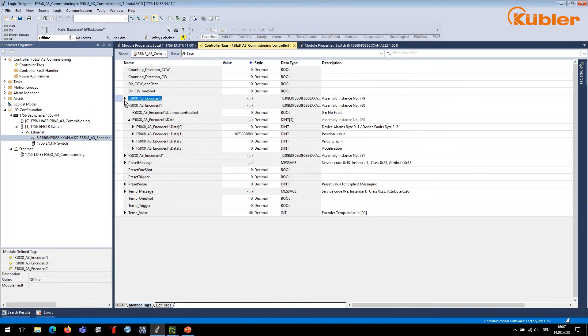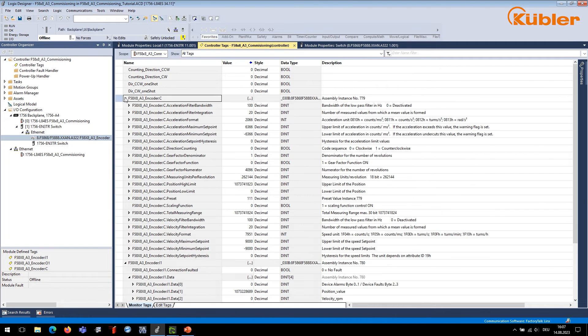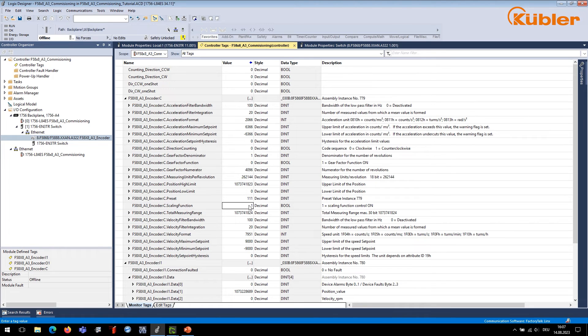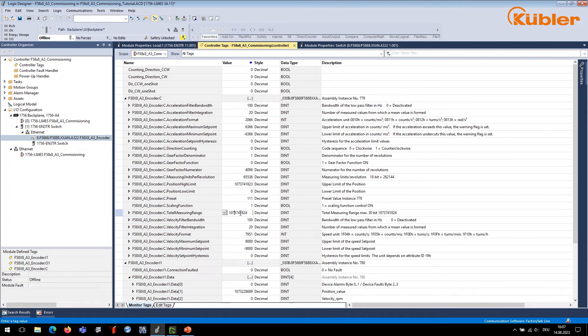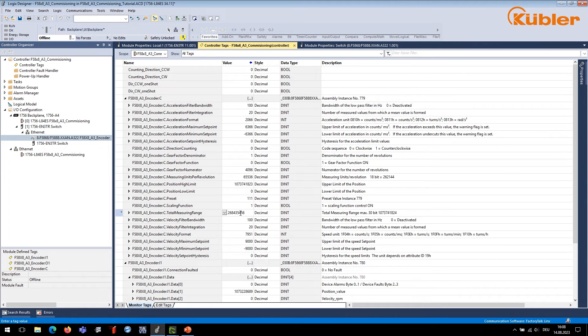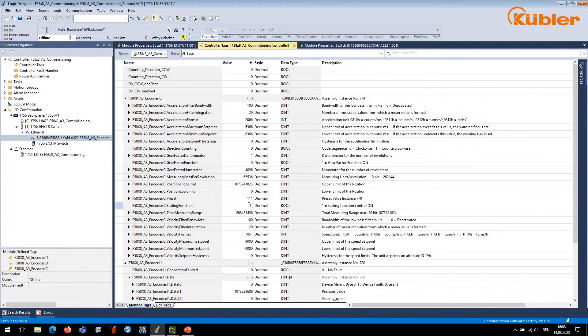To change the scaling, make sure to set the parameter scaling function to 1. Next, click on measuring units per revolution to set the MUR value. For this example, we set it to 16-bit, which is 65,536 in decimal. Click on total measuring range to set the TMR to your desired value. In this example, we set it to 28-bit, which is 268,435,456 in decimal. Once the values are set and the encoder is set to run mode, the new scaling will be active.